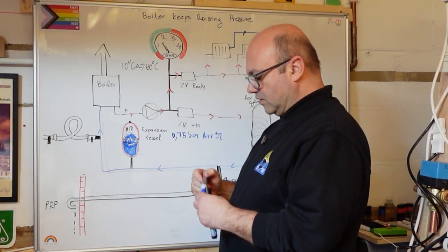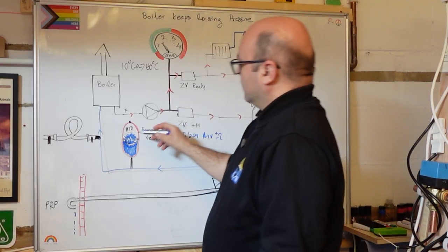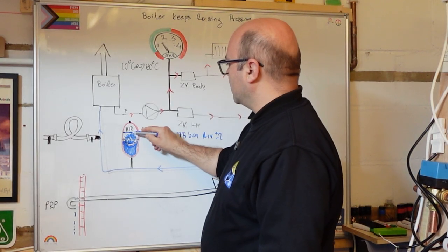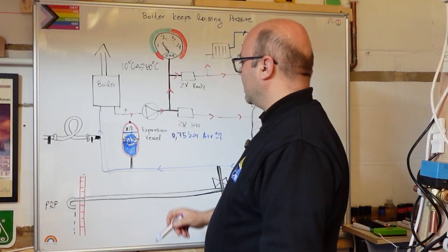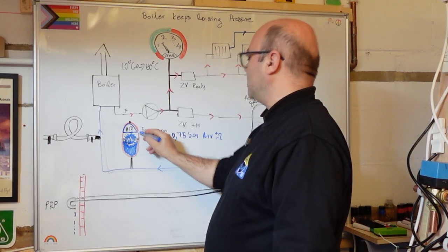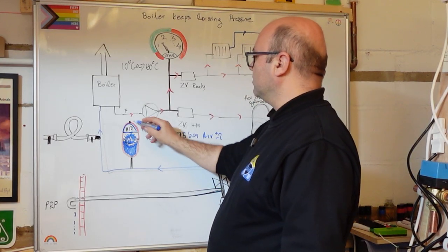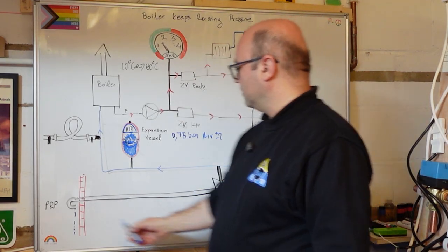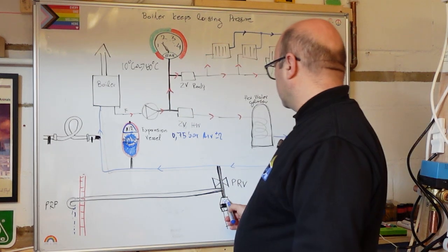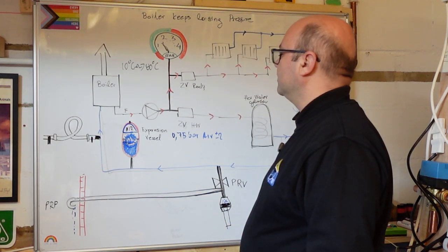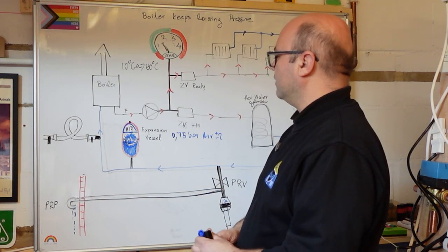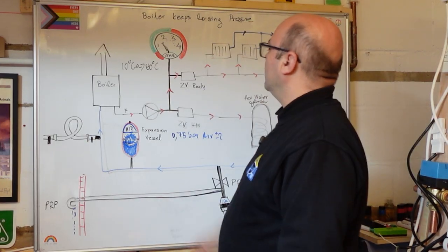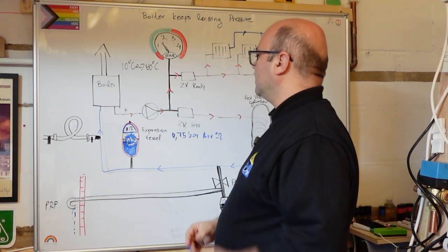As this one gets older, when the water is at 10 degrees, roughly the diaphragm is permanently here. As a result, when the water starts to expand, there is no air to bring the balance, and the excess water has to go through the PRV or the tundish. And then all we have to do is just refill it. And again and again and again that happens.